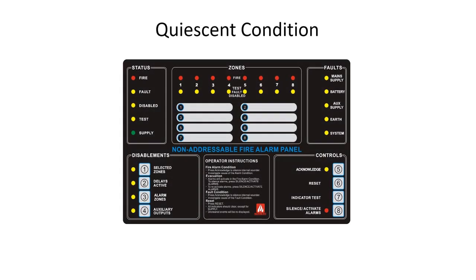The 4001 control panel reports the operational conditions defined in European Standard EN 54 Part 2. Let's briefly look at how the conditions are reported on the panel. The quiescent condition is the normal condition of the control panel. The only indicator that is on is the supply LED.